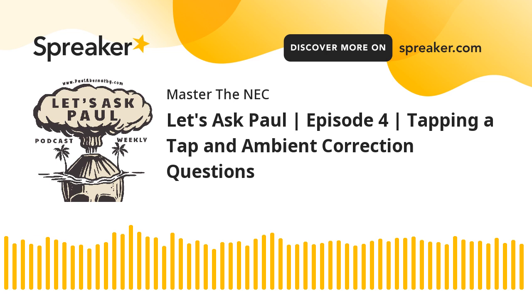And some people ask me, okay, Paul, how does that work if you've also got an adjustment? Okay, so let's introduce this question. Nothing changes in the variables except for the fact that we're going to say that we have 4 current carrying conductors now. How does that change? Well, we're not going to do anything different except for now we have the additional requirement of adding an adjustment factor under 310.15(C)(1). And that's because we have a number of current carrying conductors that exceeds 3.